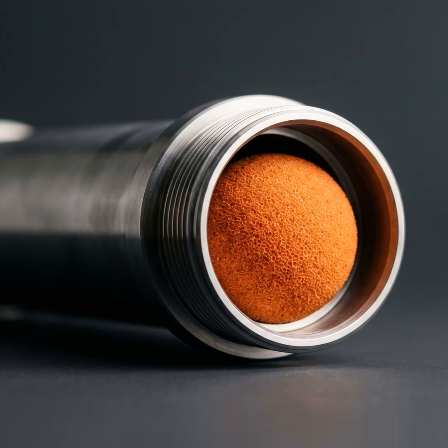Precisely. And this is where the engineers deploy their data. They show the board the math on the VFDs governed by the affinity laws. The cubic math. Right, showing how dropping fan speed by 20% cuts the fan's power bill in half. Then they add that massive financial savings on the roof to the equally massive energy savings in the basement, because the chiller isn't fighting a rock-hard layer of mineral scale anymore. Exactly. The automated sponge balls are keeping the thermal transfer perfectly clean. The combined energy reduction across the entire HVAC infrastructure is staggering. So it pays for itself. It pays for itself remarkably fast.